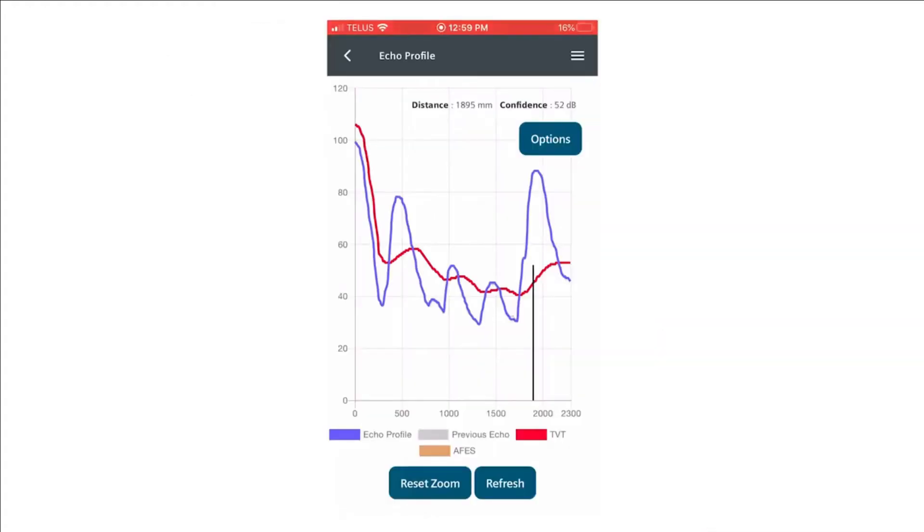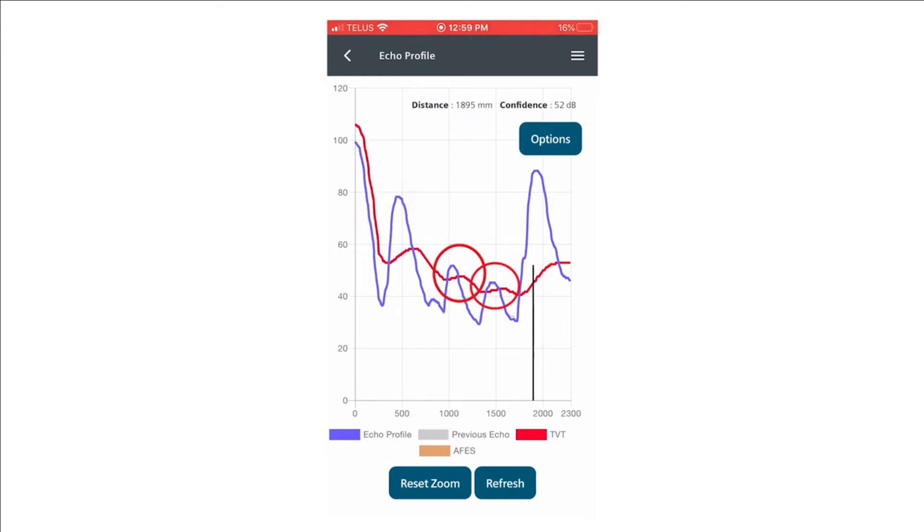This is the echo profile screen within the app, and we have a false reflection appearing at about 500 millimeters and multiples of that reflection occurring at 1,000 and 1,500 millimeters.